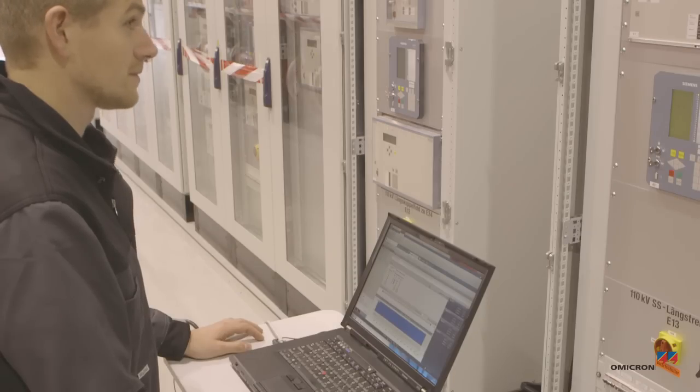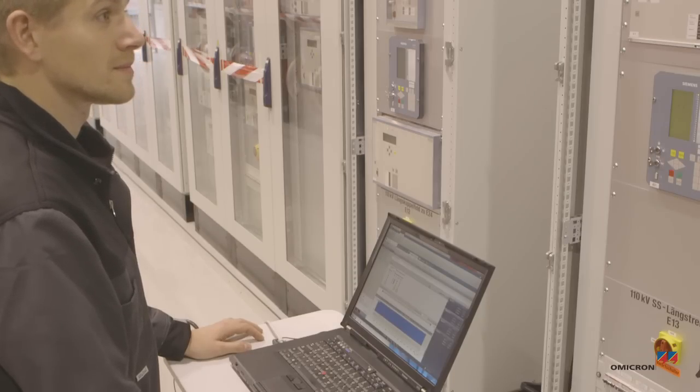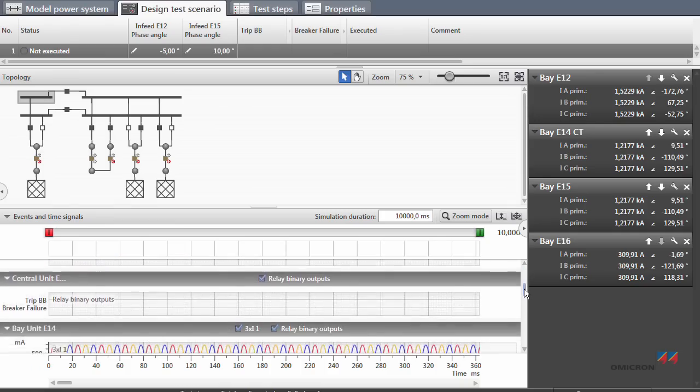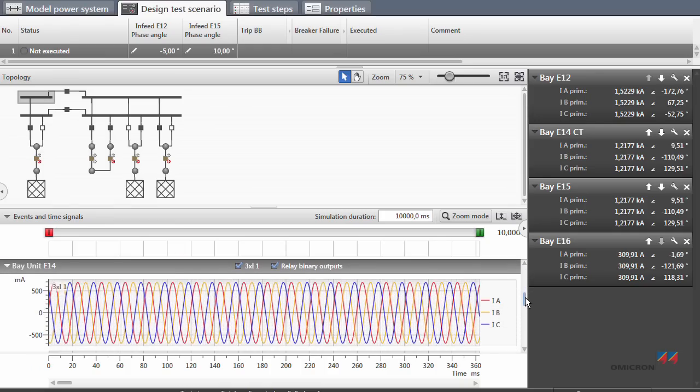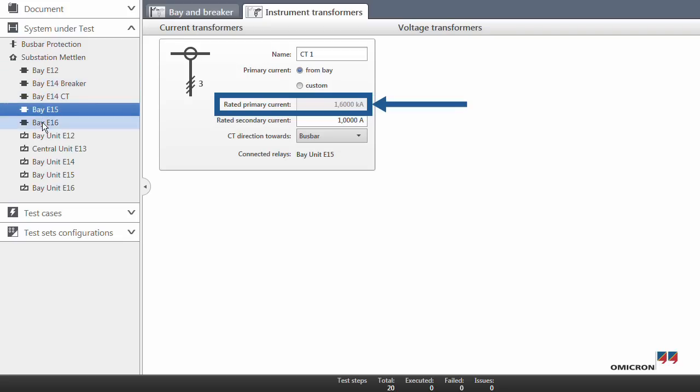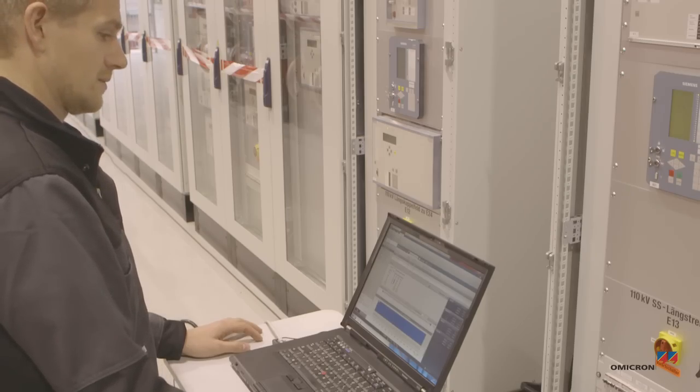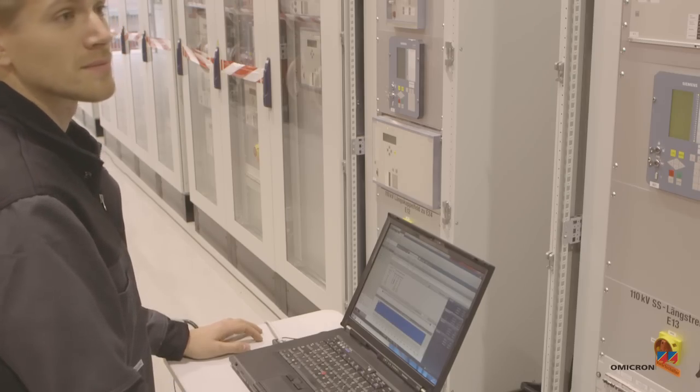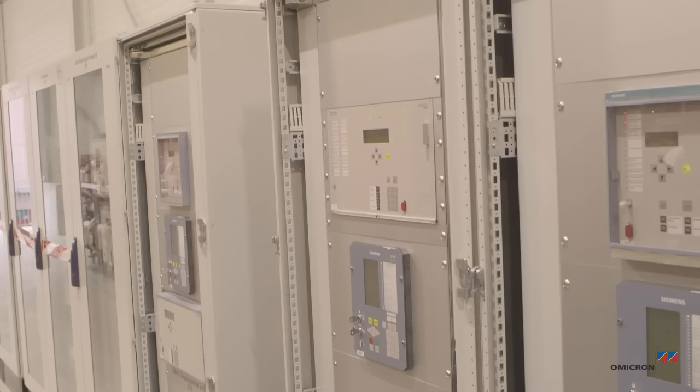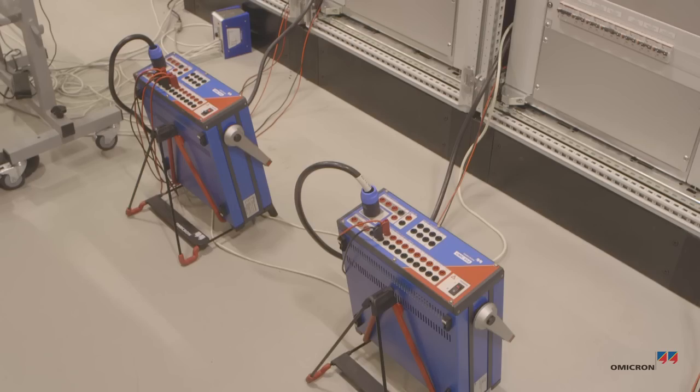Florian outputs a current to make sure that the test wiring is correct. RelaySimTest is aware of all the different CT ratios in the individual bays. As expected, the displays show the correct values. This confirms that the wiring has been done properly.